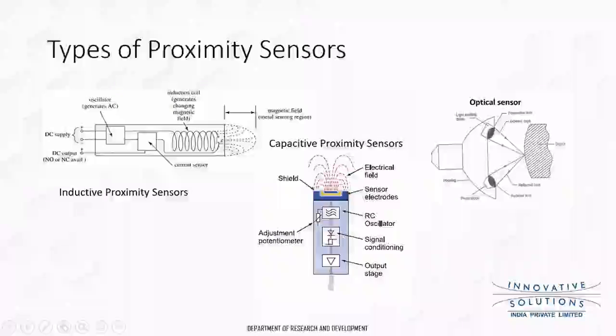You can see in the inductive proximity sensor, it is giving out some electromagnetic field in its sensing range. And if a metallic object comes within the range, the signals will be reflected or there will be additional flux generated. So when an additional flux is generated by the object, there is a change in the current which is flowing in the coil inside, and hence it will sense the presence of that object. On the other hand, in the capacitive proximity sensor, it is depending on the capacitance between the sensor and the object which has to be sensed.